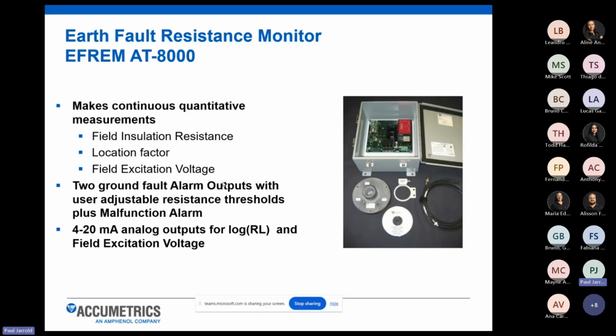That means you have a healthy generator rotor based on the value of resistance of those field windings. Over time, as a fault develops, that resistance level is going to drop because you're losing your current flow from the windings, and it's going somewhere else in the steel of the machine and the rotor forging. So you're very concerned in a power generation facility with low values of resistance. High values are good, low values are very bad.